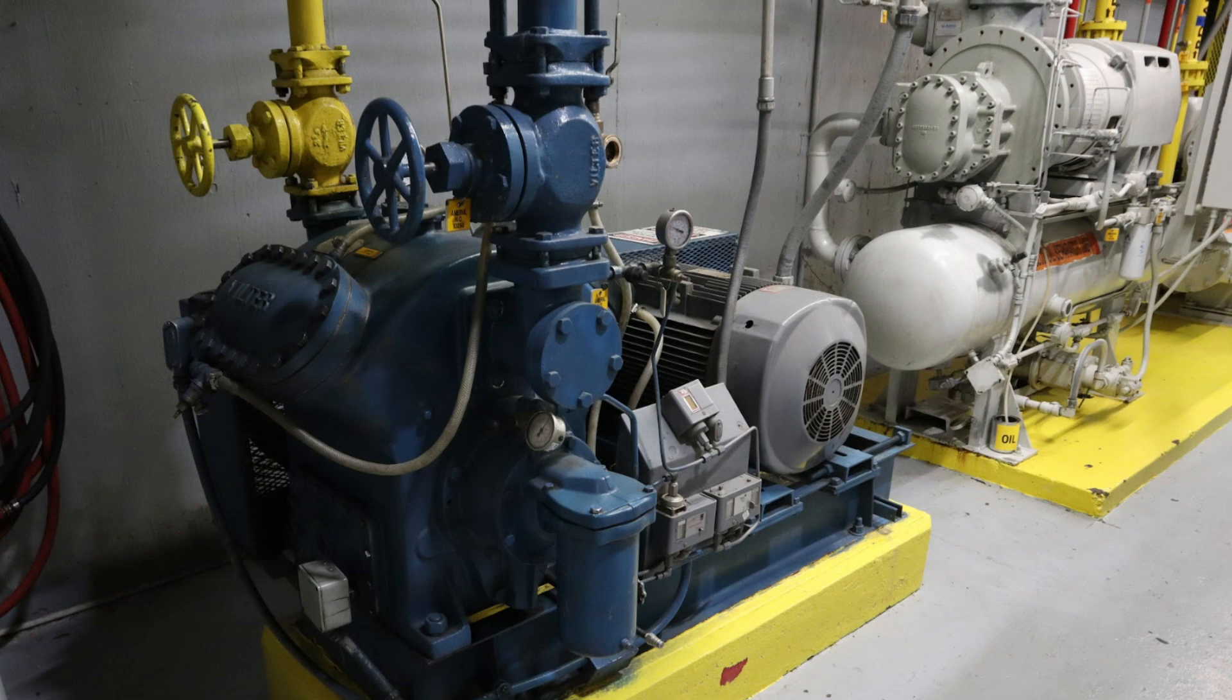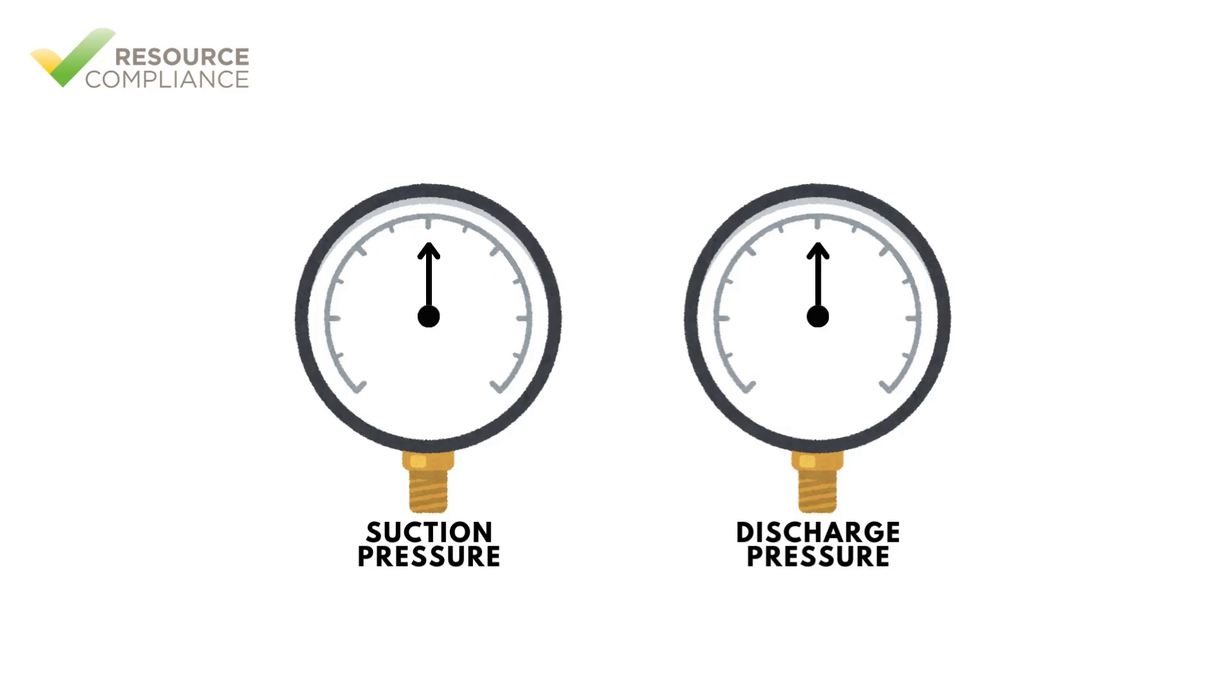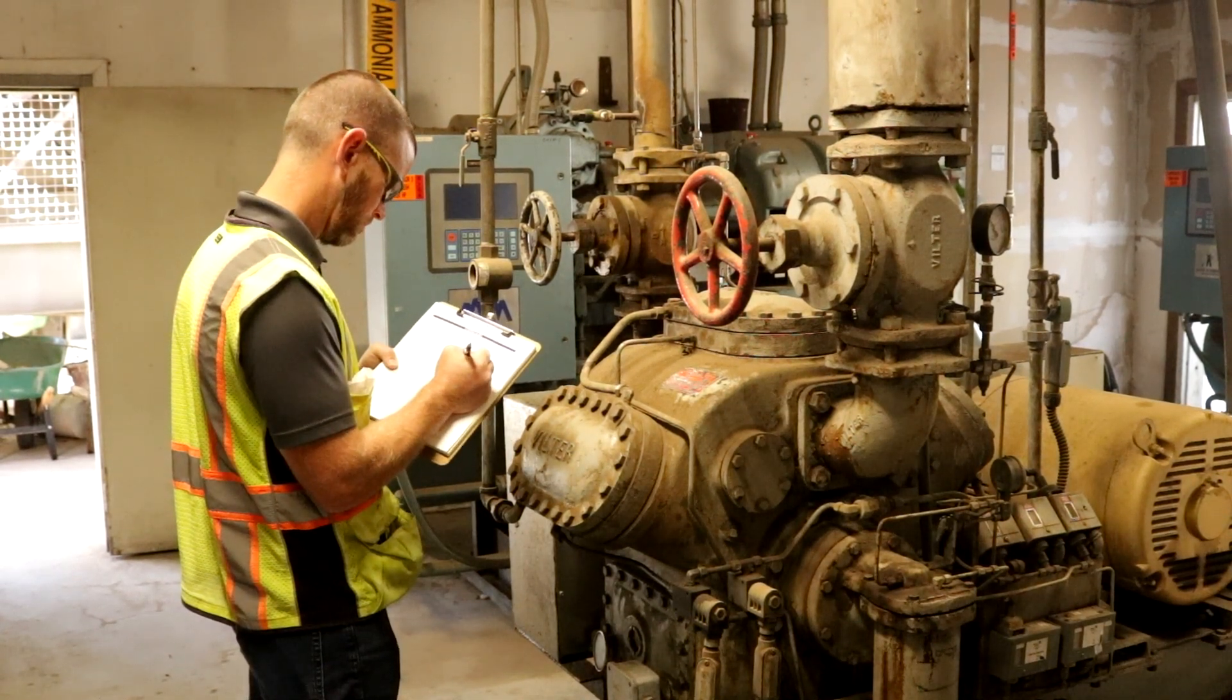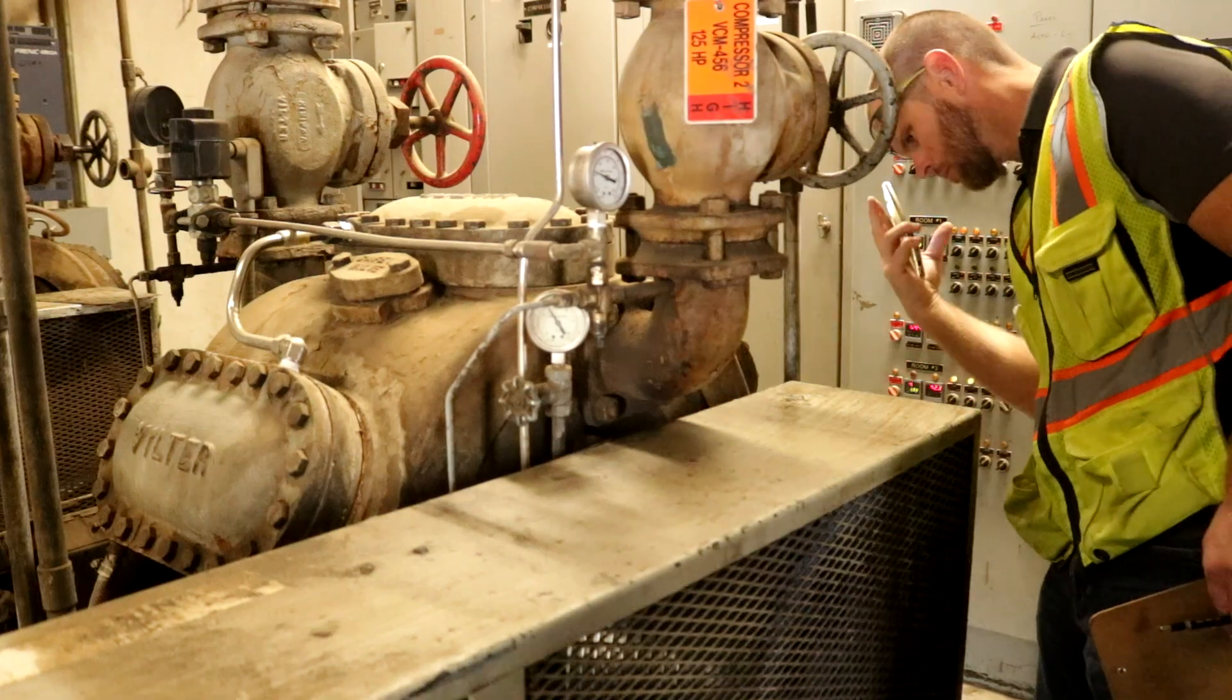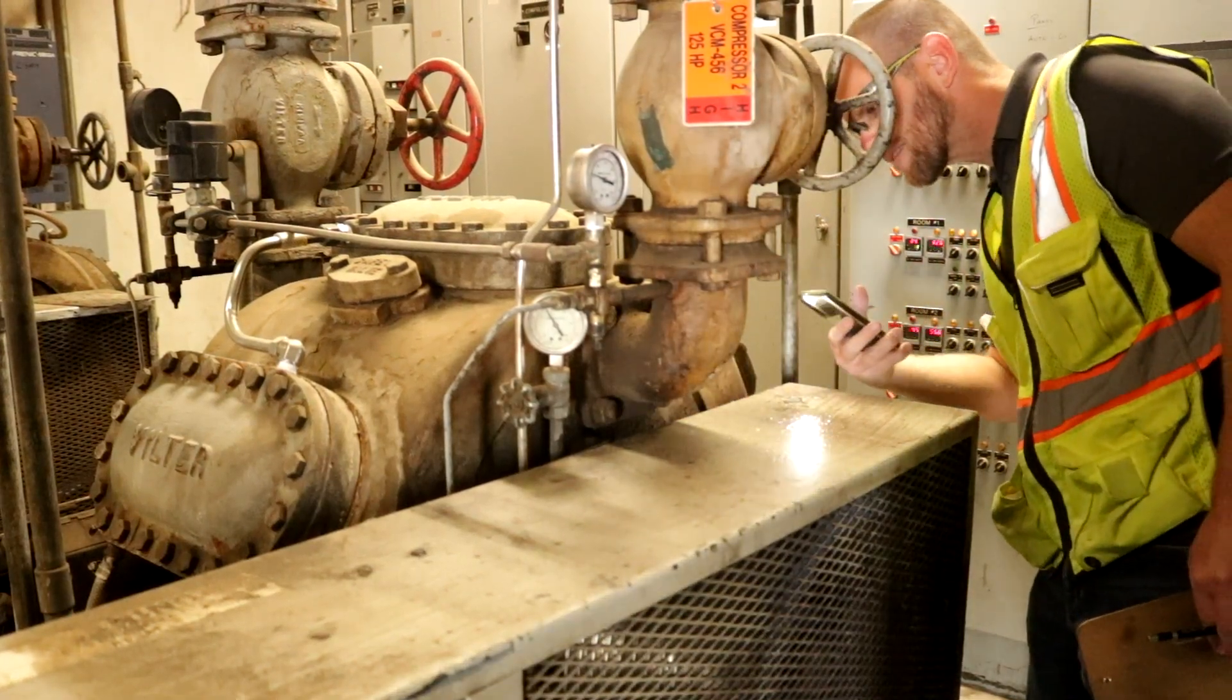Unfortunately, the compression process imparts heat into the refrigerant being compressed. This heat is called the heat of compression and is directly related to the compression ratio. A decrease in suction pressure or an increase in discharge pressure will result in a higher theoretical discharge temperature. High discharge temperatures increase friction and cause lubricating oils to break down, which result in wear and tear on the compressor.